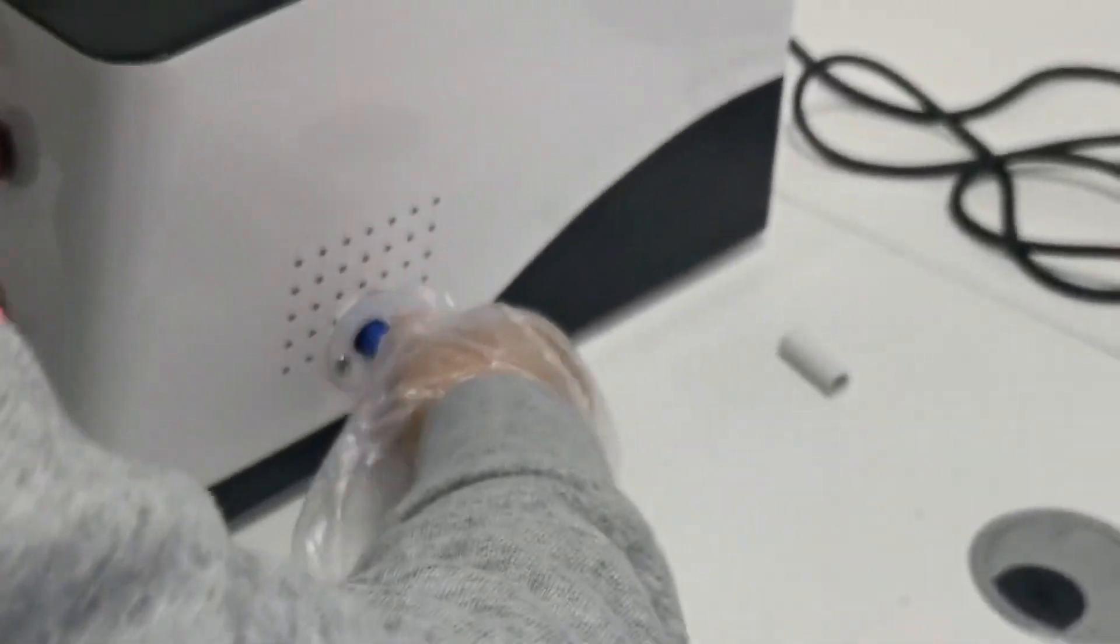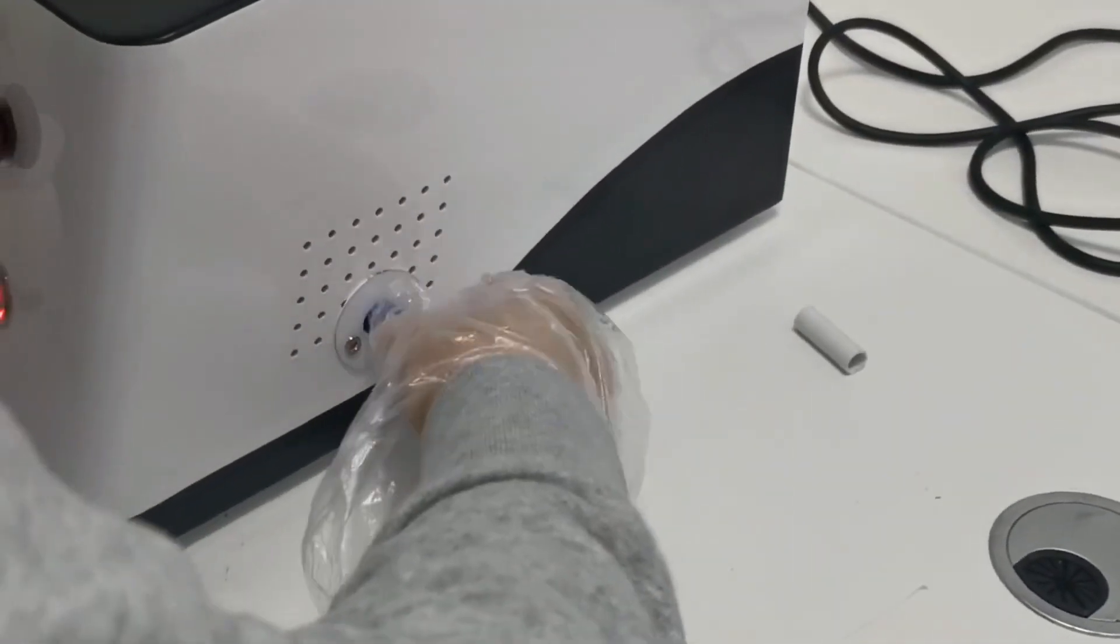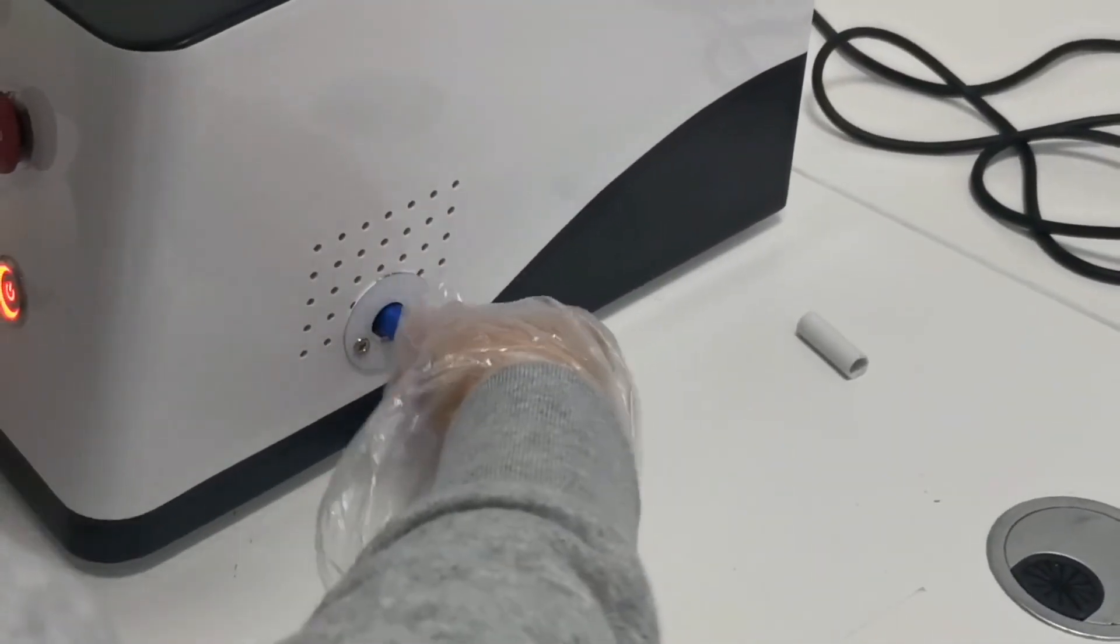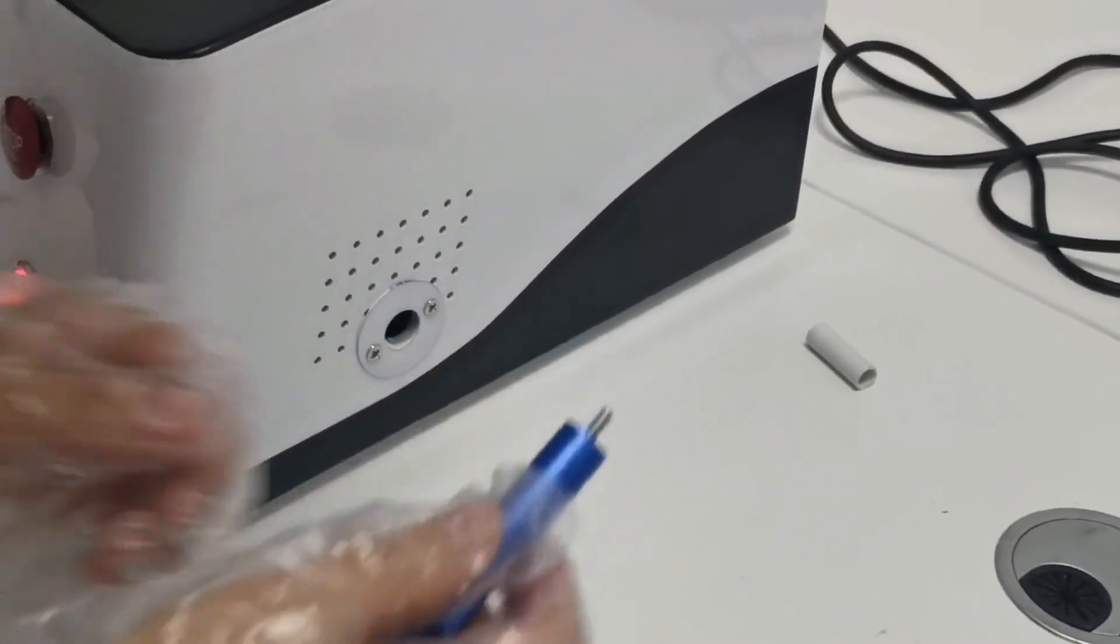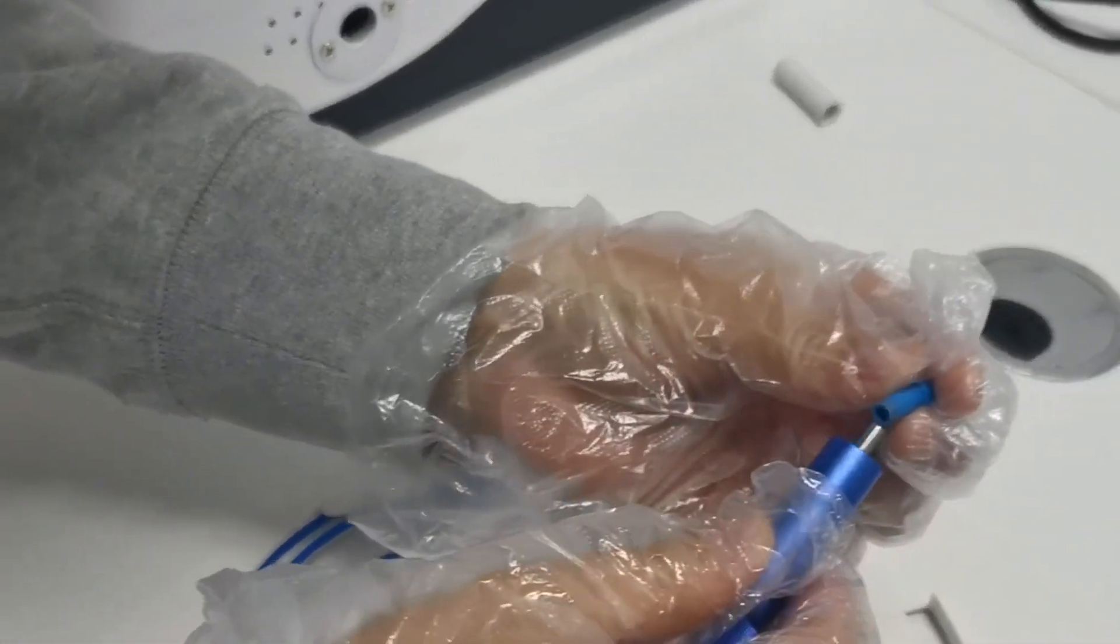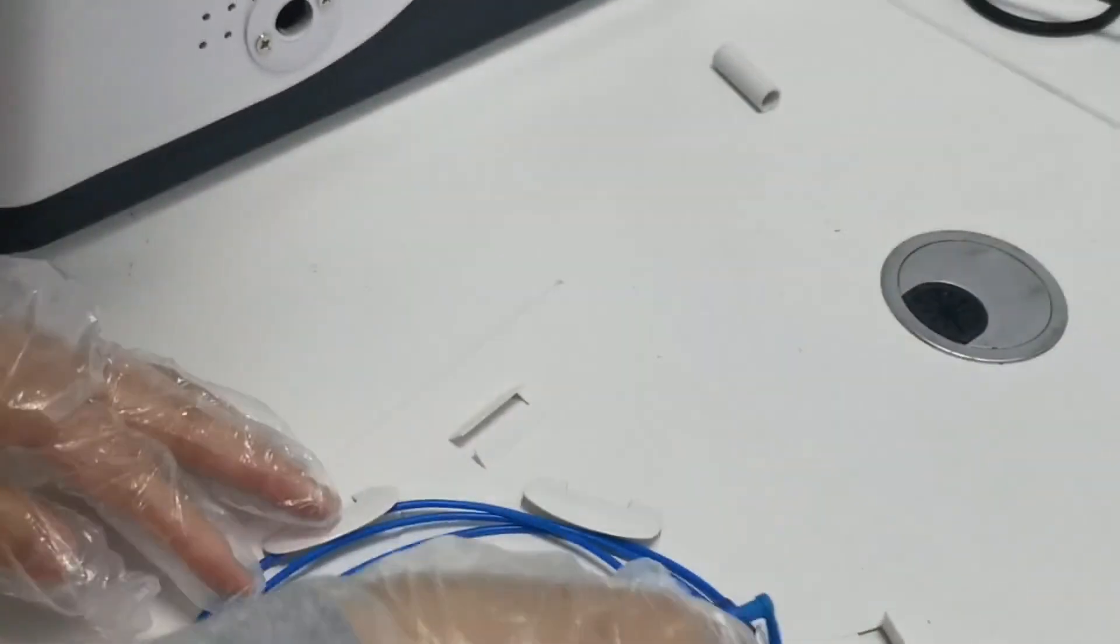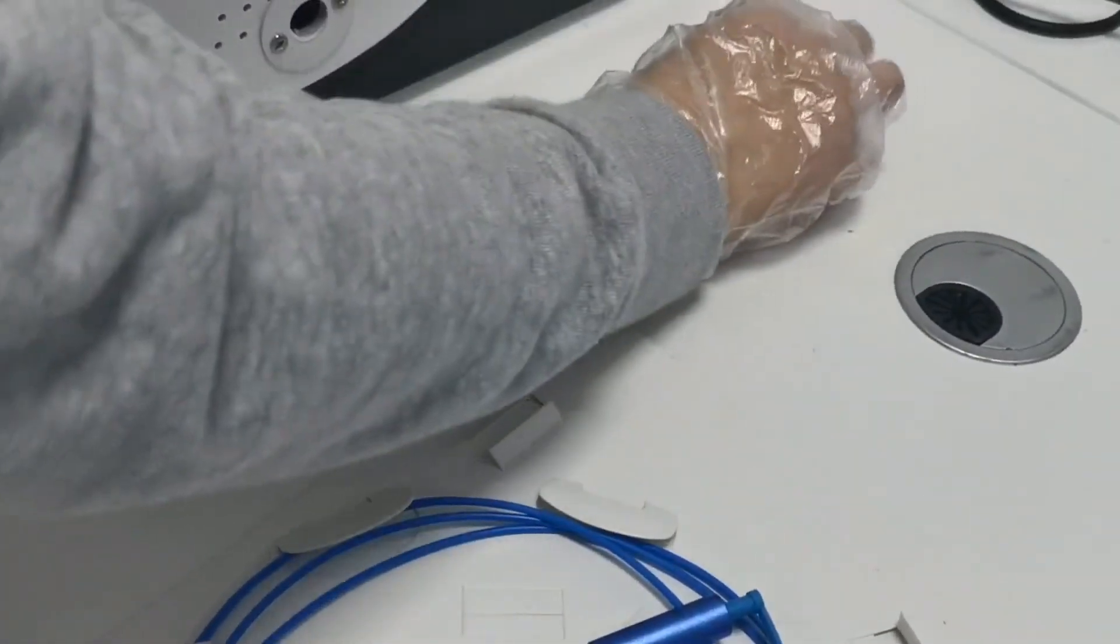After use, install the protective sleeves on the laser output port and optical fiber port to prevent dust pollution. The optical fiber port and the laser port of the host shall not be exposed at any time.